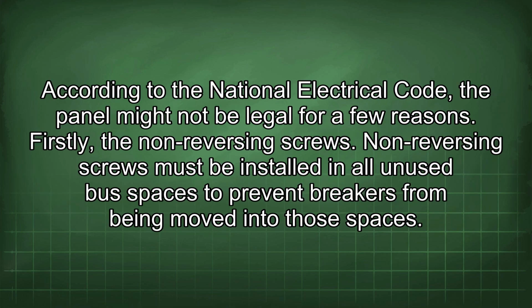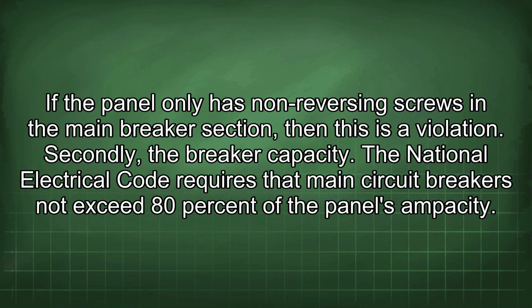According to the National Electrical Code, the panel might not be legal for a few reasons. Firstly, the non-reversing screws. Non-reversing screws must be installed in all unused bus spaces to prevent breakers from being moved into those spaces. If the panel only has non-reversing screws in the main breaker section, then this is a violation.